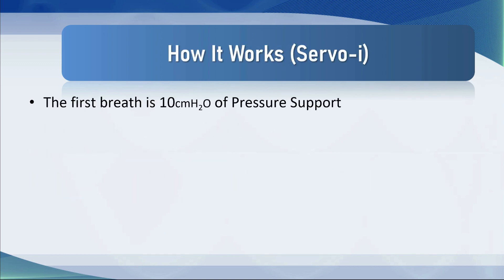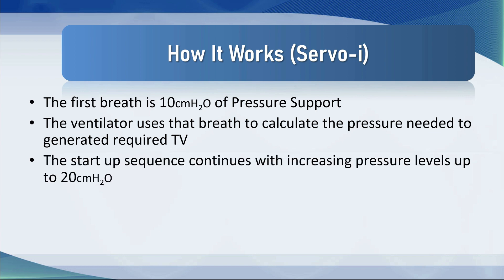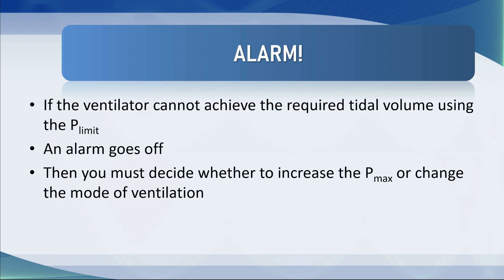On the Servo, the first breath is 10 centimeters of water of pressure support. The ventilator then uses that breath to calculate the pressure needed to generate the required tidal volume, then starts a startup sequence gradually increasing the pressure levels up to 20 centimeters of water, and then gives the patient the pressure support level it thinks it needs. Subsequently the ventilator may make changes from breath to breath, but it limits those changes to a maximum of plus or minus three centimeters of water — it doesn't give 20 centimeters in one breath and five in the next. If the ventilator cannot achieve the required tidal volume using the pressure limit, an alarm goes on and you need to decide whether to increase the Pmax or change the mode of ventilation.